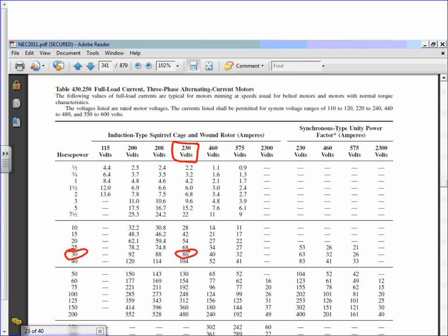Now, Darren is looking at me and says, Chad, you didn't do this one for the motors. Remember what the motors had. What did the motors have? Horsepower. We already know that. The HVAC equipment doesn't have a horsepower, do they? They give you KVA, so they have to find the horsepower rating for this thing. Any questions, guys, about how we came up with 30?